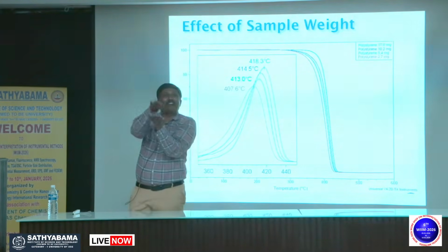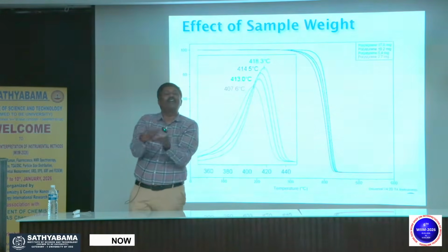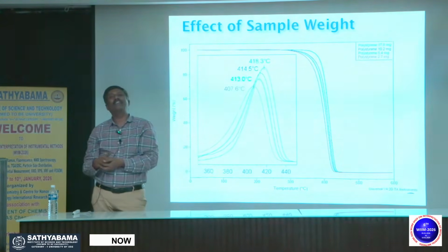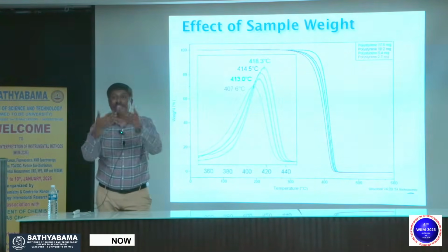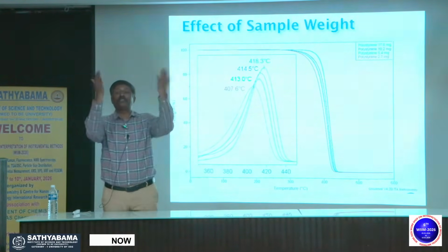If you have a hill kind of thing, more layers, what will happen? Again thermal lag. You don't reach the real temperature that you want. It takes time and the instrument is running.